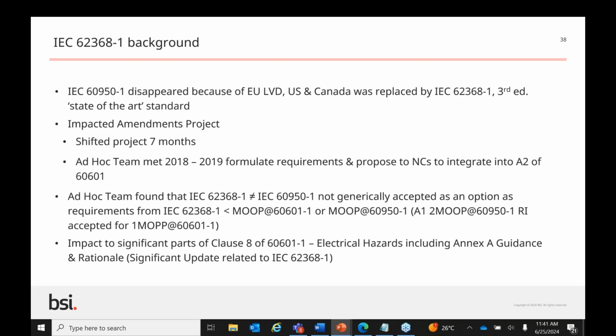So the ad hoc team was formed, which I also was part of that team. And we found that 2 means of operator protection at 62368-1 levels were not equivalent to 2 means of operator protection at 60950 levels. And in the previous edition of the standard, 2 means of operator protection for 60950 was equivalent to 1 means of patient protection. But if 2 means of operator protection at 62368 wasn't equivalent to 2 means of operator protection of 60950, we had an equivalency problem. So SC62A couldn't generically accept it as an option, and so we had to pivot somehow. So we had to figure out what was going on. Next slide will explain it a little more.